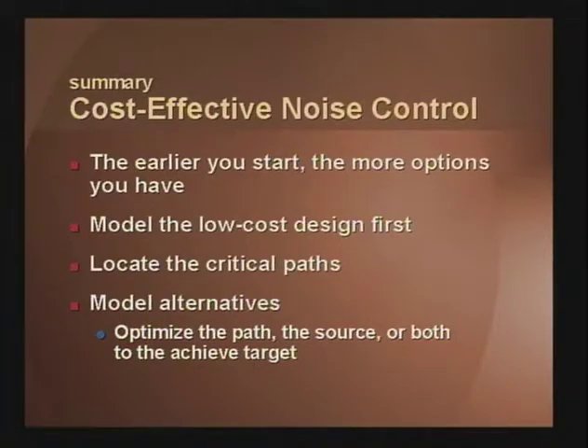In terms of cost-effective noise control, some simple guidelines are in order. Number one, the earlier you start, the more options you have. Back in the design phase, it's very easy to cost optimize a system. Second, model the lowest cost design first. Why not start with the simplest and the cheapest? And then locate the critical paths, then model the alternatives or the options you need in order to get the source and the path down to the right levels so that you achieve your acoustical target.